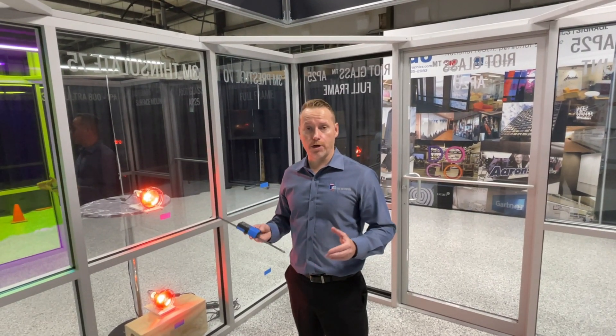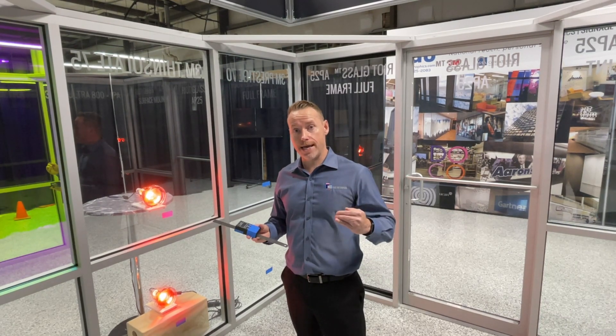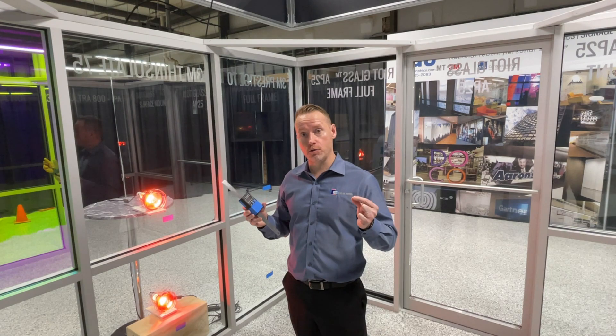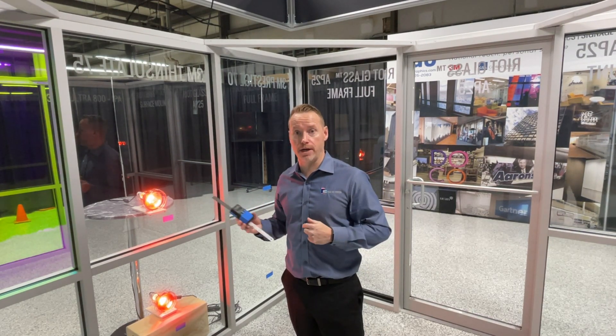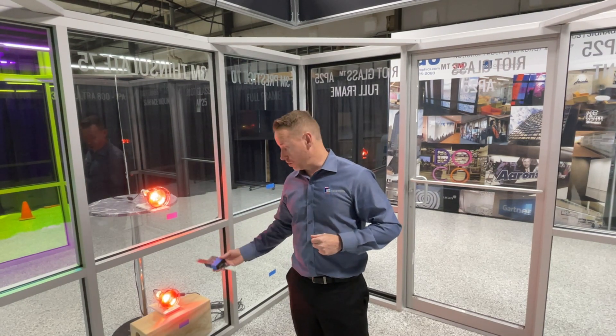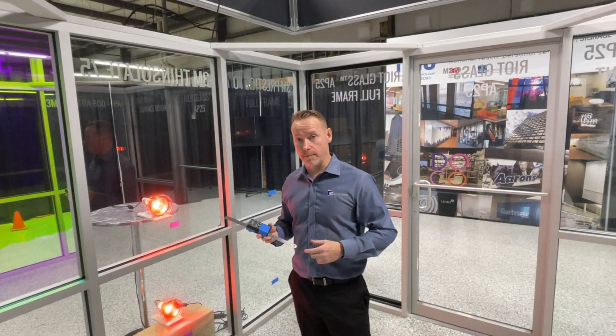Fantastic for any buildings where you need a window upgrade from an insulation standpoint and you don't want to change the look of the glass. Now we're going to demonstrate how the 3M Thinsulate 75 reduces solar heat gain by using this BTU meter to measure BTUs per square foot per hour transmitted through the glass — where we have the Thinsulate 75 installed versus where we do not — on a quarter-inch single pane clear glass using an infrared heat lamp.